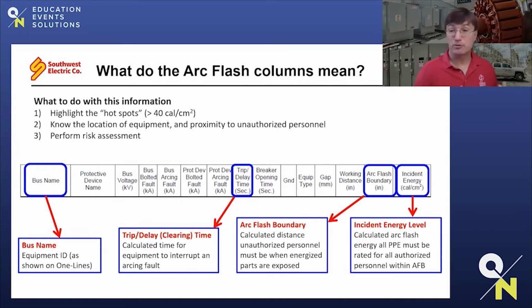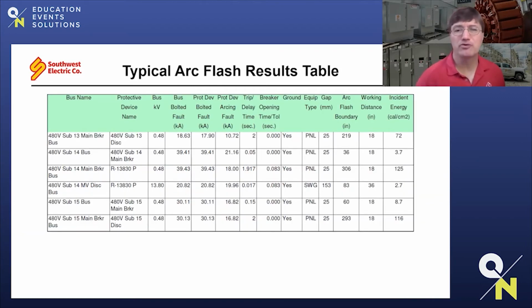We also want to know where the location of this equipment is going to be. And we also want to perform a risk assessment. What's the foot traffic like around this equipment? Is this isolated where very few people ever come in contact with this equipment, or do people walk by this constantly throughout the day? If an arc event were to occur suddenly, how many people could it affect at one time? So here's our typical arc flash results table.